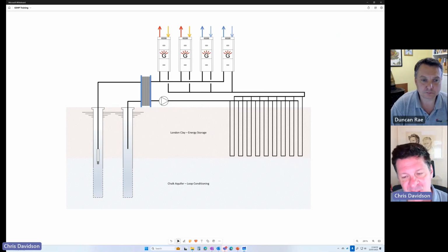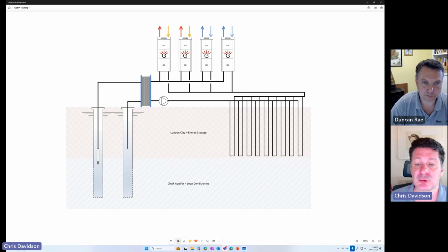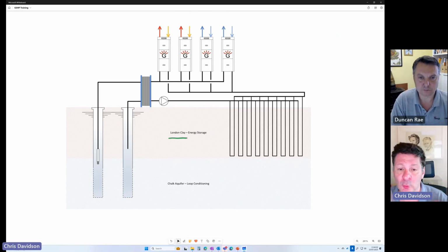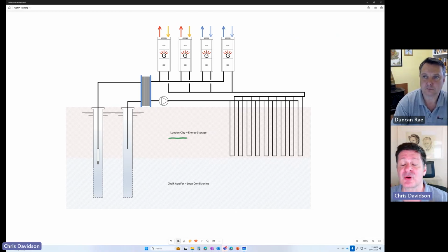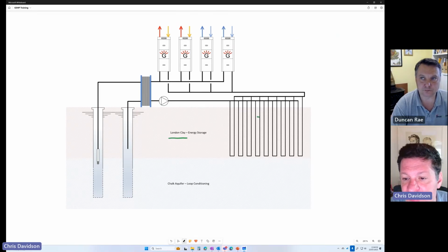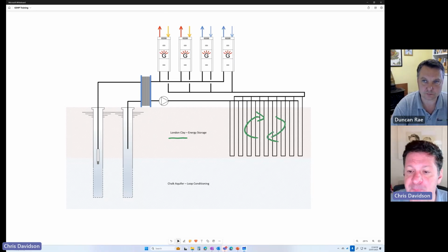The brief on this project was to do the maximum we could with the geology available to us. In this instance, there were unusually big and deep piles on the building, so we utilised those piles to put loops inside the London clay. The London clay is quite a low conductivity ground condition, but it's got very good energy storage characteristics. So that becomes our interseasonal energy store, and we're actively managing the temperature in that interseasonal energy store. We can do that in several ways.